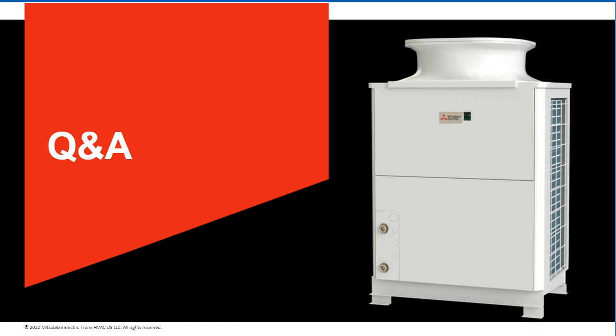All right, great. Okay, so will the CO2 in the system degrade over time? Will the unit need the CO2 recharged at some point? Yeah, since it is a closed loop system, no. As long as there's no leak or anything on the system, it will not degrade over time. Just like any HFC refrigerant out there, as long as it's closed and you don't have any other outside influences, you will not have to recharge it or adjust things over time.